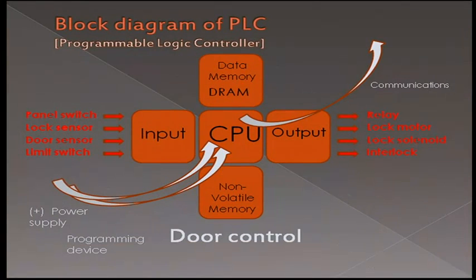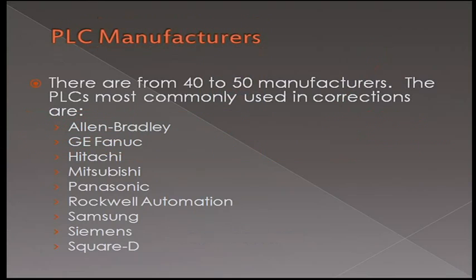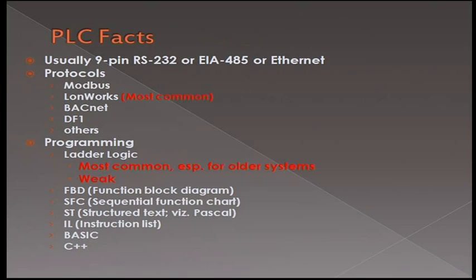This is a diagram of how the PLC works — basically in and out, basically multiplexing. There are a ton of manufacturers of PLCs; these are just some of the common ones. PLCs can communicate via different methods: serial connections, Modbus, BACnet, DF1, others, and also clearly Ethernet — they're sticking these on the LAN as well. There are different ways to program them. Ladder logic is probably the most common because it's easiest — it's designed for someone who's not a computer programmer to use. It's just linear, straight through. If this, then that. Just like a ladder.